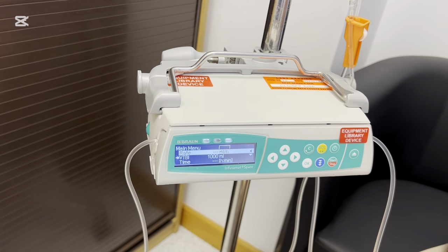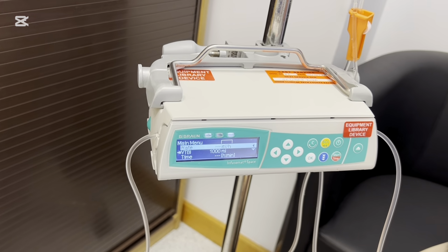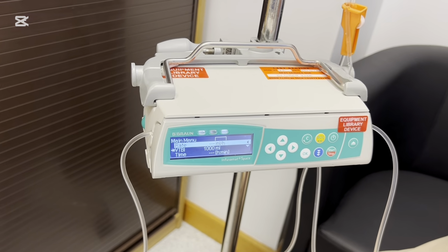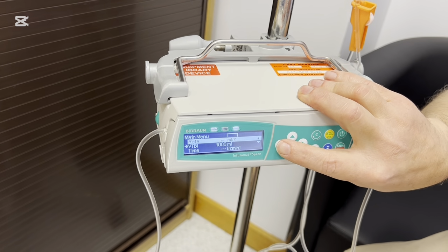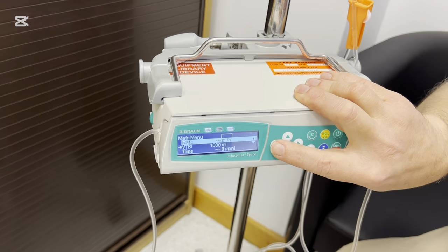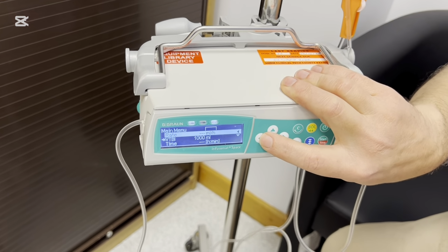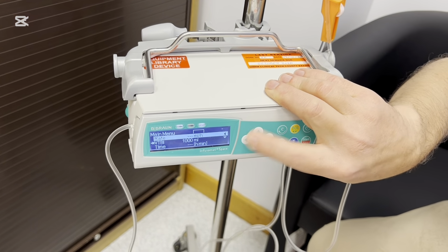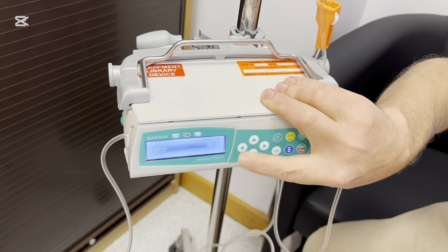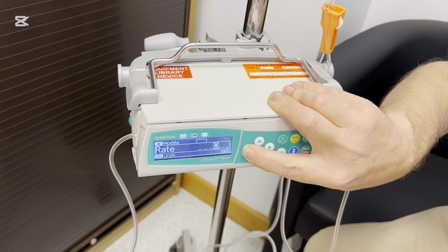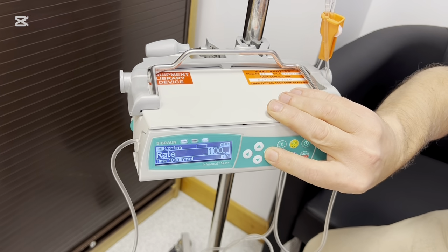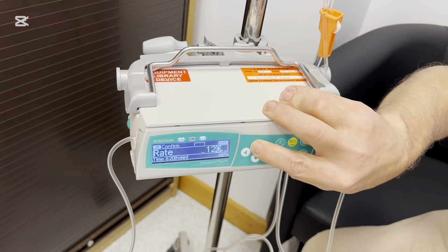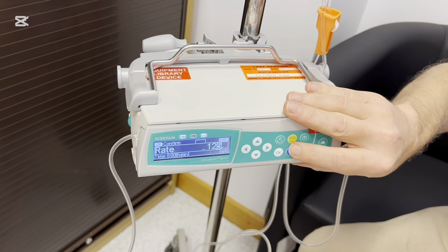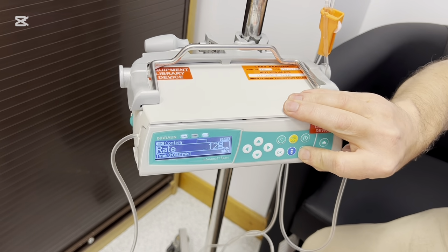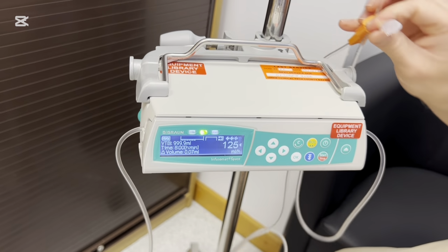So you can either set mils per hour, or you can select to deliver the bag over a certain time period. So you can do one or the other. Don't get confused and try and do both, because it'll just counteract and use the last one that's been set. So if we're going to administer this over 8 hours, then we're going to select 125 mils an hour. So again, you're going to enter the 1, 2, 5. If we press start, then it will start to pump.